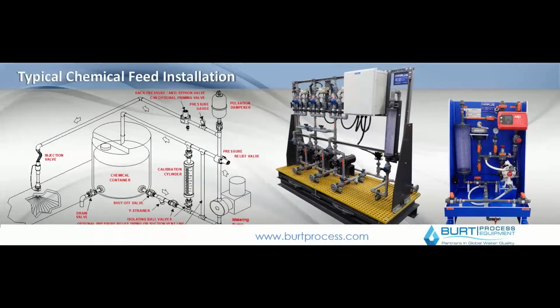Here you can see a couple of different examples. Regardless of the specific style of chemical feed system utilized, they have a lot of very similar components, which I just went through. On the left, you have a chemical metering pump, or a different pumping technology. You're drawing your chemical, and you have a strainer, isolation, calibration columns, pressure relief, a back pressure valve to put pressure back on the pump, a pulsation dampener, and then your injection valve. At its heart, 90% of chemical feed systems incorporate almost all, if not all, of these basic components.